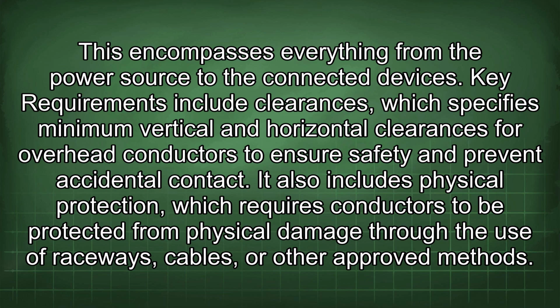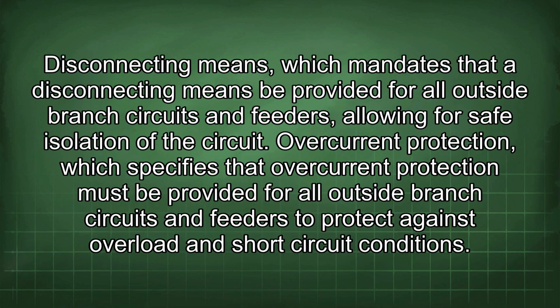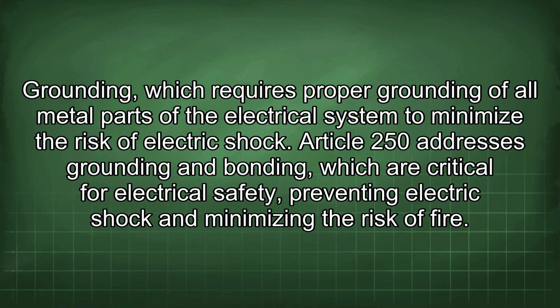Key requirements include clearances, which specifies minimum vertical and horizontal clearances for overhead conductors to ensure safety and prevent accidental contact. It also includes physical protection, which requires conductors to be protected from physical damage through the use of raceways, cables, or other approved methods. Disconnecting means, which mandates that a disconnecting means be provided for all outside branch circuits and feeders, allowing for safe isolation of the circuit. Overcurrent protection, which specifies that overcurrent protection must be provided for all outside branch circuits and feeders to protect against overload and short-circuit conditions. Grounding, which requires proper grounding of all metal parts of the electrical system to minimize the risk of electric shock.